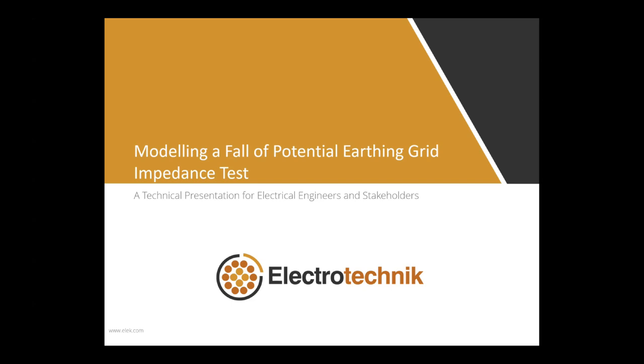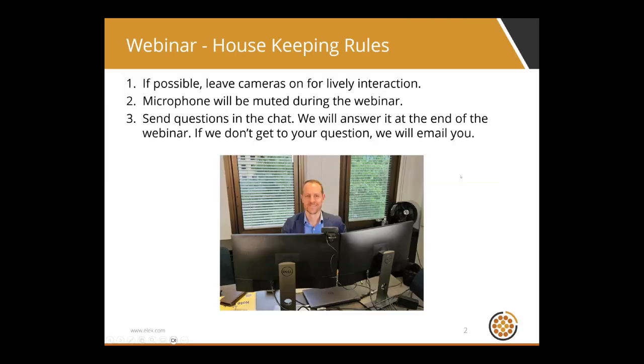In this free webinar hosted by ELEK Software, we will look into the principles and limitations of the fall of potential method. We will see why we have to accurately measure soil and earthing models in grid impedance testing, and how software can help us to optimize test setups and to predict the results. During this webinar, we will show you how to simulate a fall of potential test, how soil resistivity is impacting your accuracy, and we'll also show you some practical techniques of determining optimal current and voltage electrode placements, interpreting the results, and mitigating common errors.